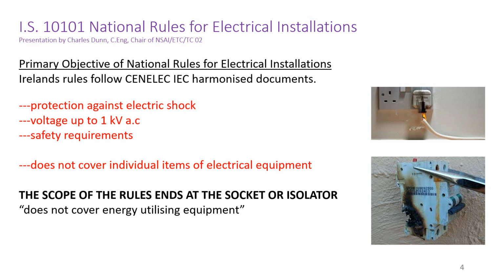Another key point to note is that IS 10101 deals only with the wiring installation up to the socket or isolator. IS 10101 does not cover energy utilising equipment. NSAI and international standards authorities have a suite of standards dealing with electrical equipment that is plugged in or connected to the isolator, such as televisions, cookers, air handling units, hot water generators, etc.